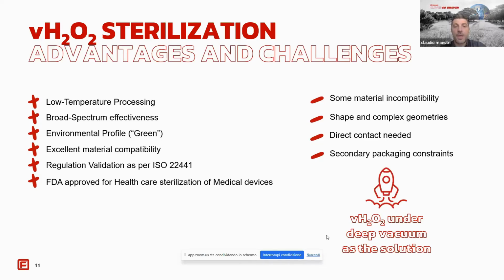Environmental profile: green. H2O2 is considered a green sterilization modality because its active vapor breaks down into oxygen and water vapor. This eliminates the dangerous emissions associated with ETO. Excellent material compatibility. As we have seen on the slide before, H2O2 has an excellent compatibility with a wide range of polymeric materials and metals. It's suitable for several products, including general surgical instruments, endoscopes, implants with electronics, pharmaceutical containers, and prefilled syringes. Regulation: validation per ISO 22441, as we have seen on the slide before. FDA approval for healthcare sterilization of medical devices.